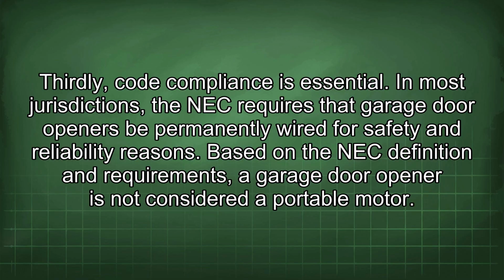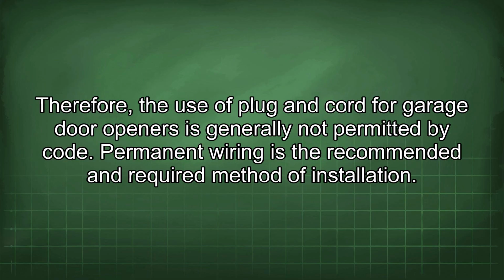Based on the NEC definition and requirements, a garage door opener is not considered a portable motor. Therefore, the use of a plug and cord for garage door openers is generally not permitted by code. Permanent wiring is the recommended and required method of installation.